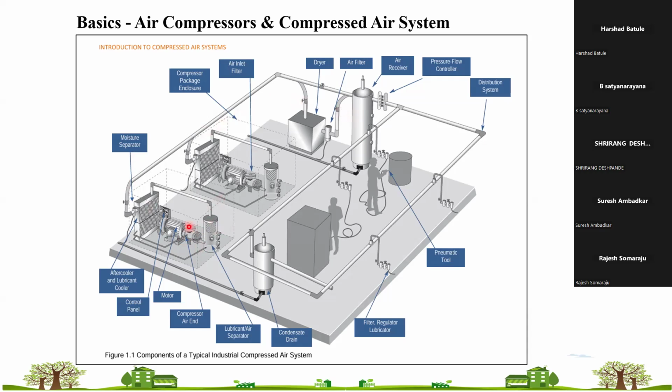To reach that final 7 bar, the time taken by that compressor is called the pump up time, which is T in the formula. It is the time taken to fill that particular compressor receiver.